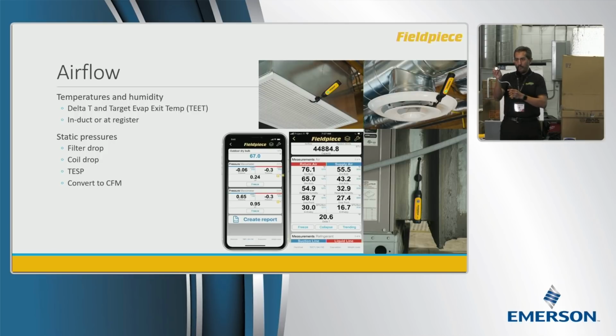Does it matter which way we insert this probe into the duct? Absolutely, right? One thing is this static pressure probe has a magnet built in right here, so when you stick it into the ductwork, it holds there, hands-free. On the part that's external, there's a red arrow that helps us orient the tip in the correct direction in the ductwork, which is parallel to the airflow.